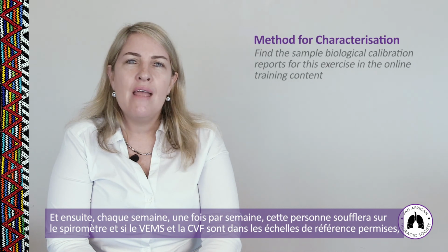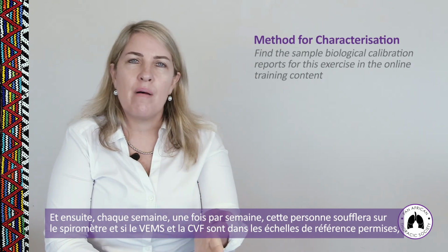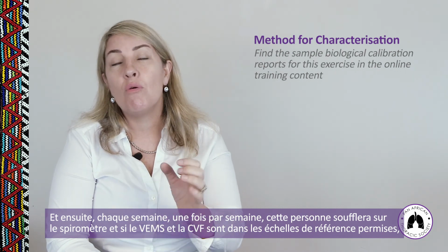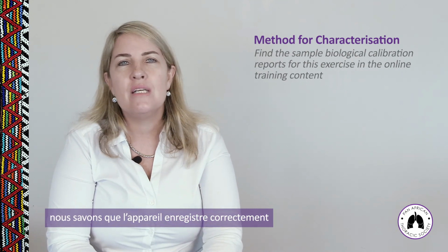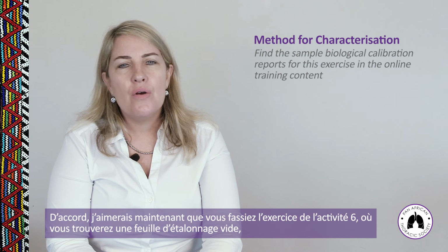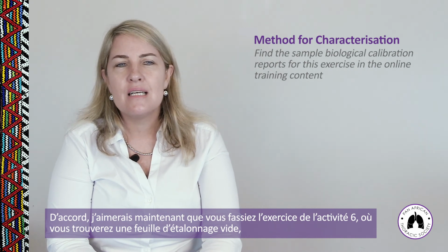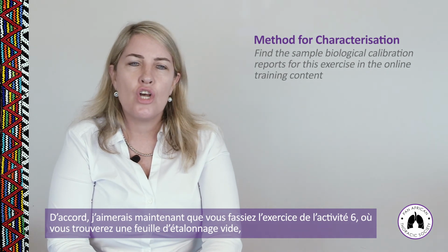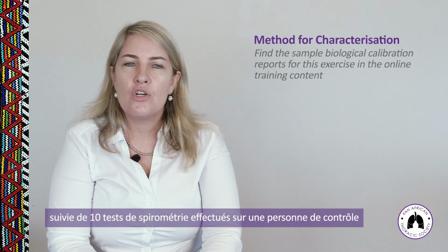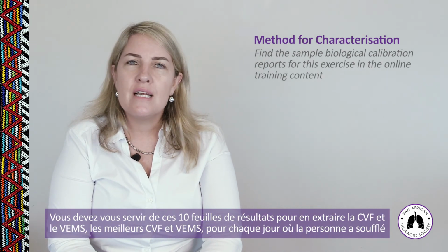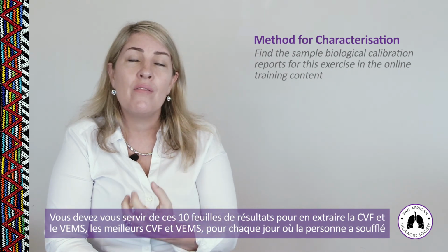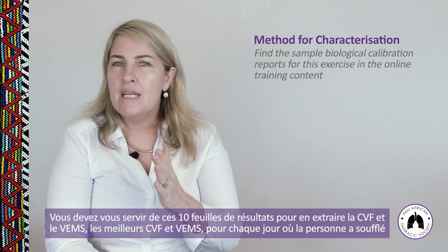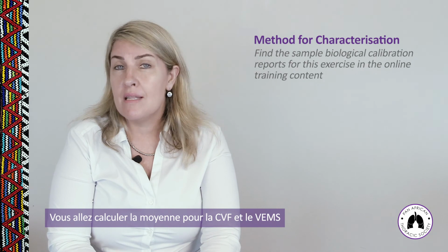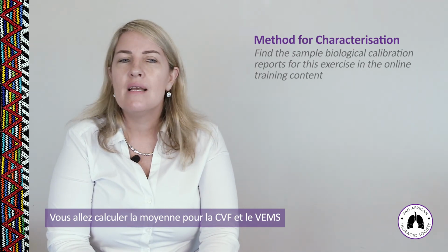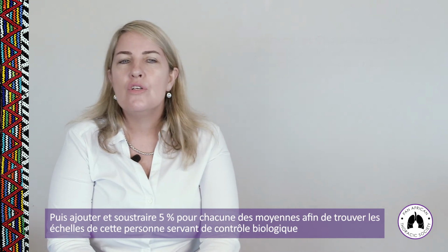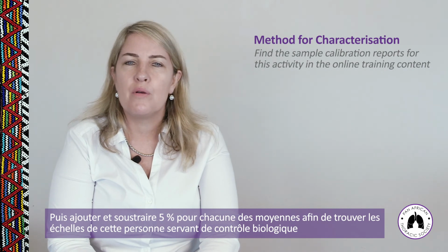Now, thereafter, once a week, this person will blow onto the spirometer, and if the FVC and FEV1 fall within those allowed reference ranges, we know that the machine is reading accurately. So I would like you to do the exercise now, activity 6, whereby you will find an empty biological calibration chart followed by 10 spirometry tests conducted on a control person. You need to use those 10 spirometry printouts to extract the best FVC and the best FEV1 for each of the days that the person has blown. Work out the mean for the FVC and the mean for the FEV1, and then add and subtract 5% to each of those to get your ranges for that biological quality control person.